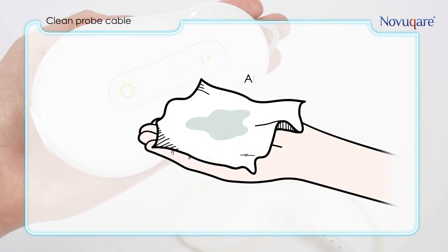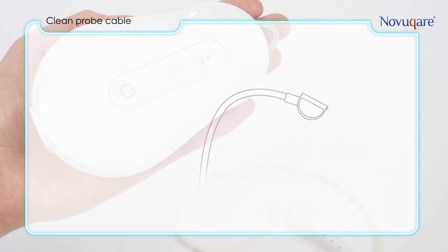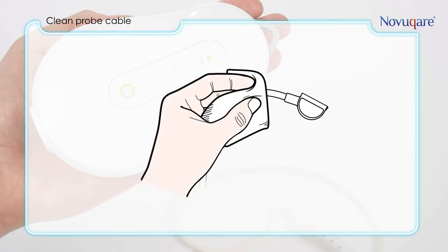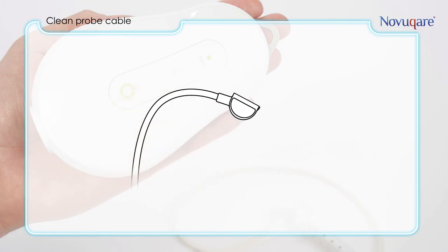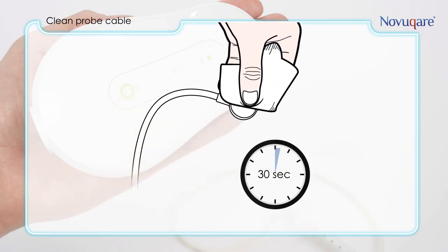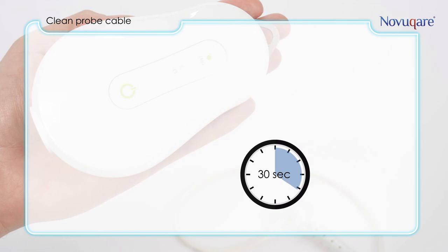Put alcohol 70% on a clean tissue in your ungloved hand and hold the probe. Remove the glove from your other hand to hold the end of the cable. Disinfect the first 20 centimeters of the cable for 30 seconds while constantly keeping the surface wet with alcohol. Throw the tissue away and let the cable dry.